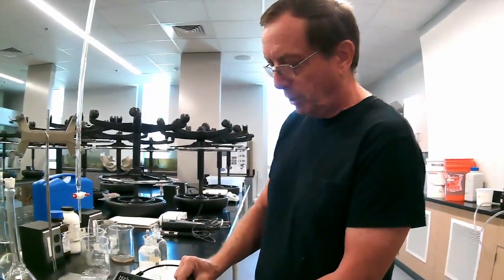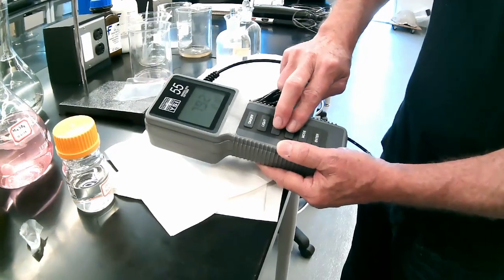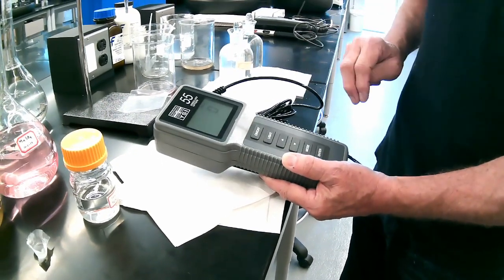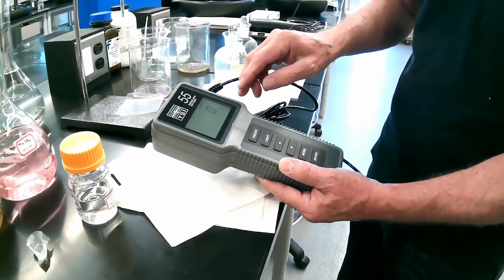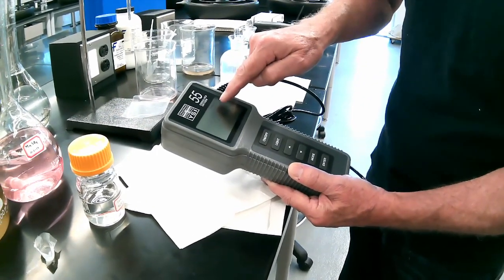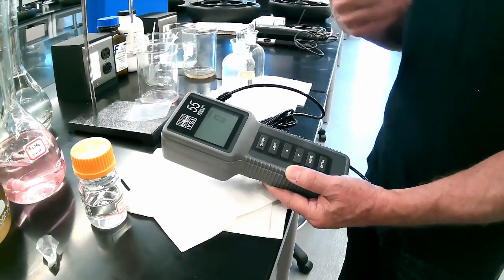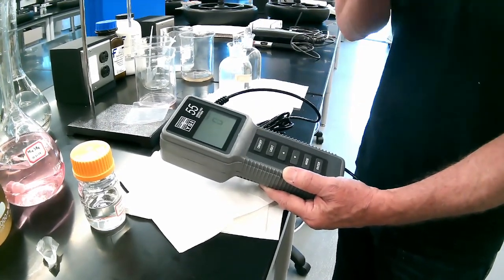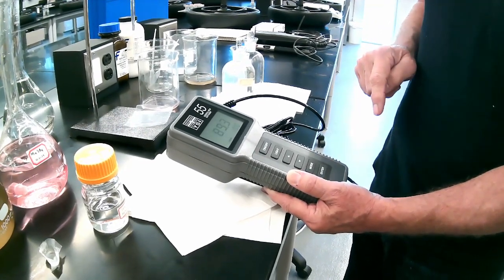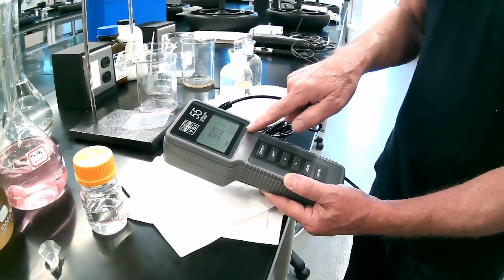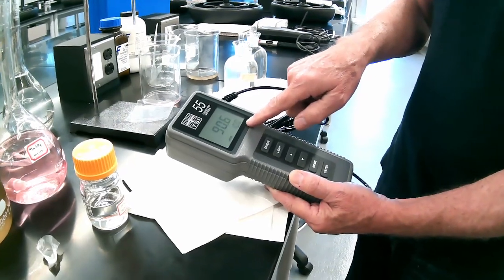So the first thing we do is we take these two arrow buttons and push them simultaneously, and that sets up the calibration feature inside the little computer. Right now, you can't read it, but it's reading altitude. We're in Florida. Our altitude is 0. We are at sea level, so we'll just go ahead and enter that. Okay, and then you'll see that it's switched to a number here. The number on the bottom is 100%.